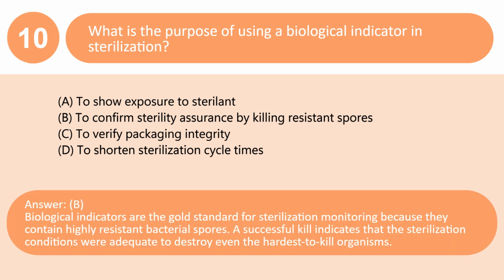Answer: B. Biological indicators are the gold standard for sterilization monitoring because they contain highly resistant bacterial spores. A successful kill indicates that the sterilization conditions were adequate to destroy even the hardest-to-kill organisms.